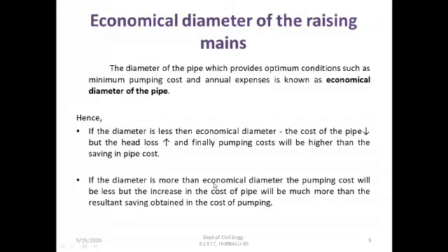The diameter of the pipe can be reduced by increasing the flow velocity through the pipe, but the increased velocity will lead to higher frictional head loss and thus increased cost of pumping. Hence, although the diameter and the cost of pipe can be reduced by choosing a higher flow velocity, the horsepower of the pump required will increase, thus increasing the cost of pumping.